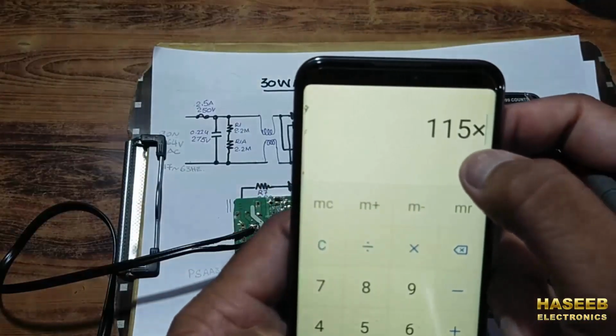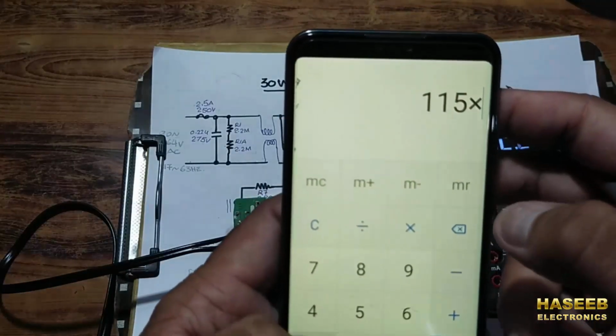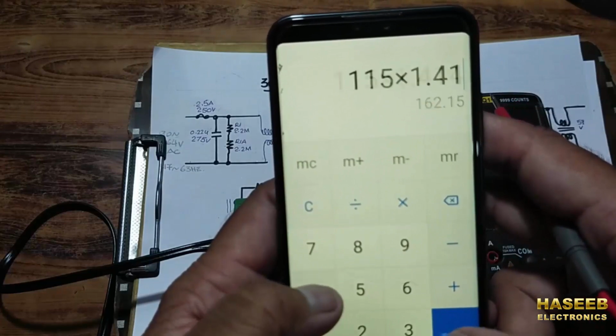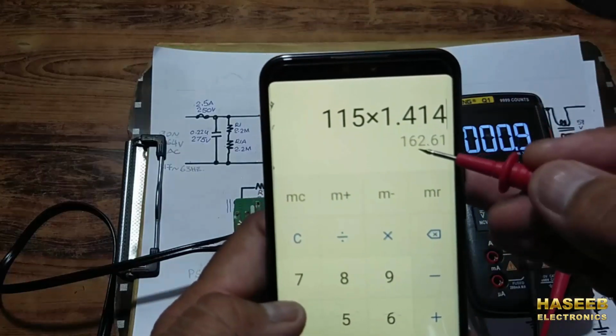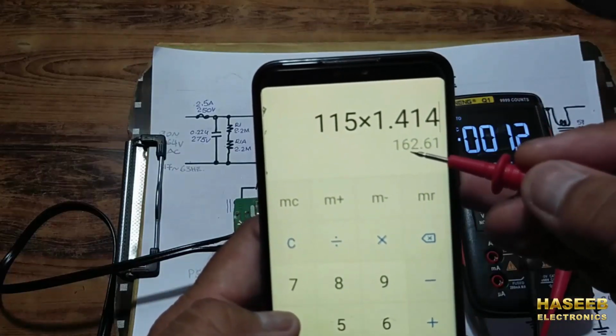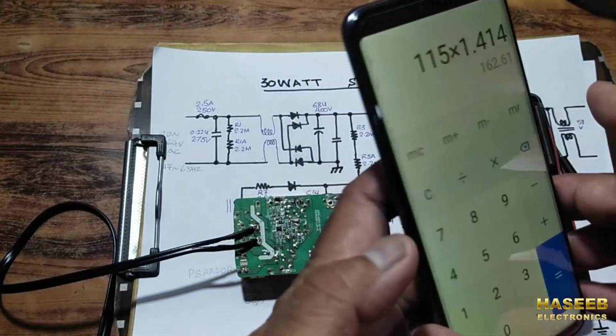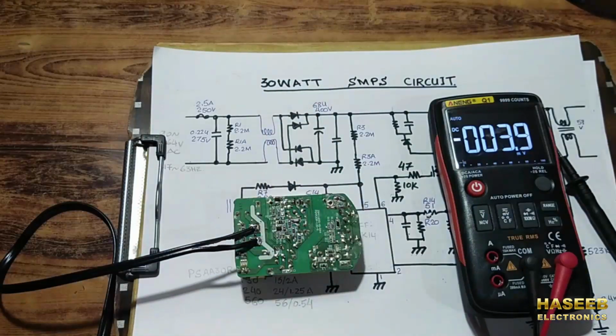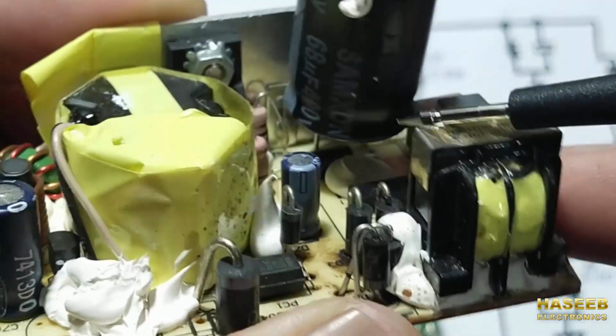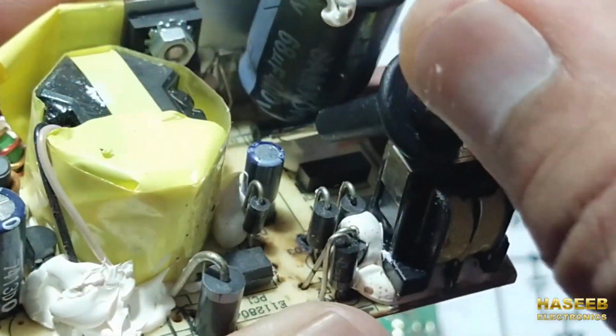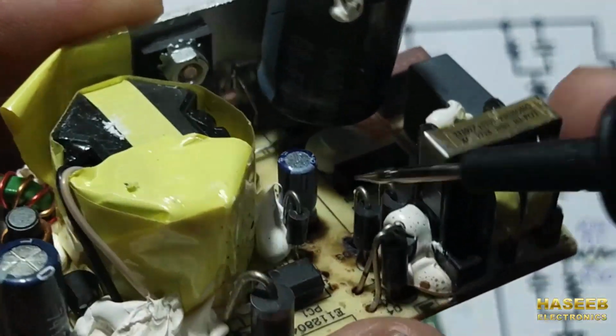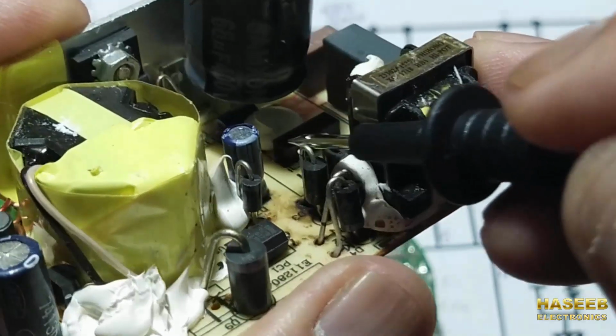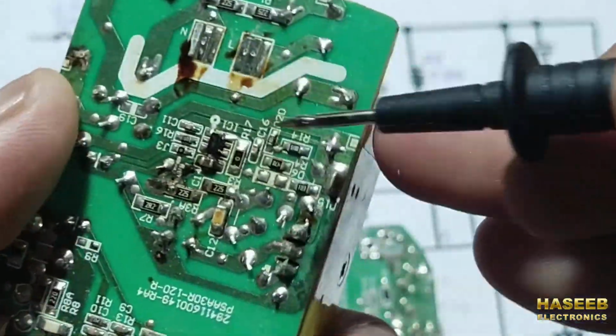If our line voltage is 115 volt, multiplying by 1.414, in that case 162 volts should be available at the capacitor, because it is a universal power supply. From the positive line we have a jumper here that looks black in color, and this jumper is connected.